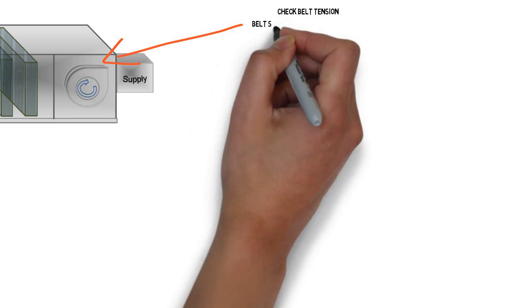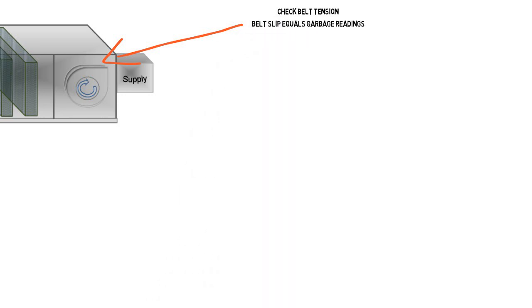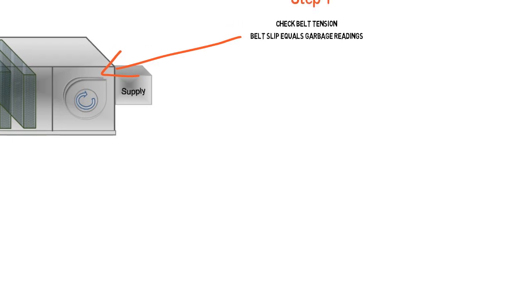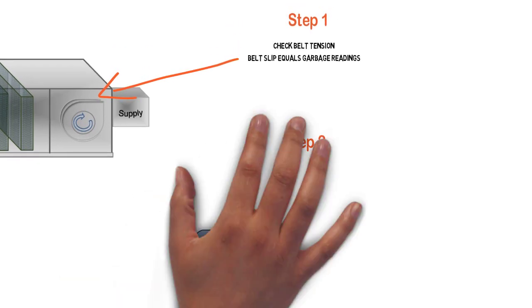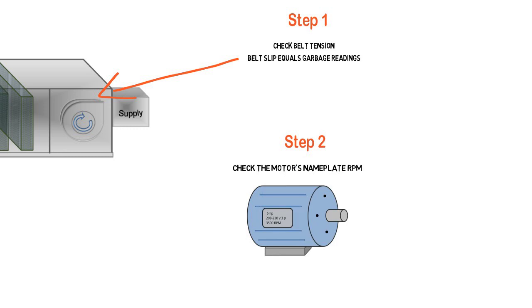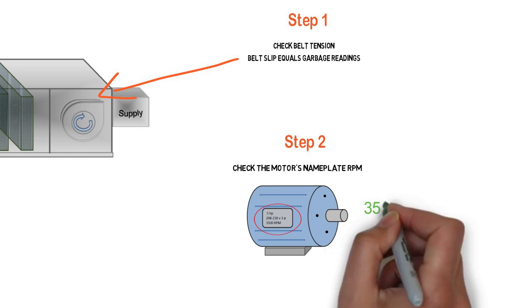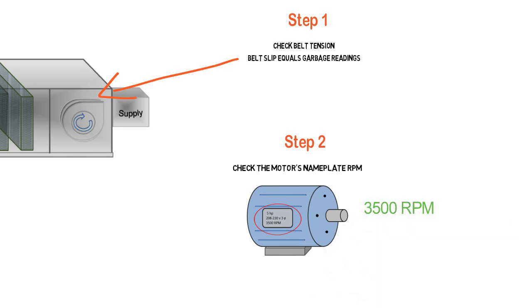First, we're going to make sure the belts are tight. Because if the belts are loose, we're going to have slip. And if we have slip, all our readings are going to be garbage, which means our airflow calculation will be garbage. While we're in that compartment, we're going to check the RPM on the motor's nameplate. In this example, it's 3,500 RPM.